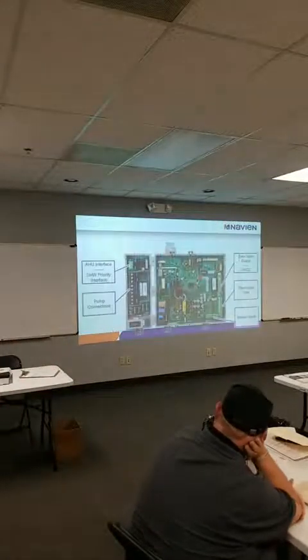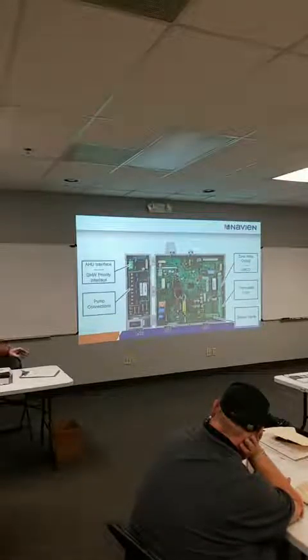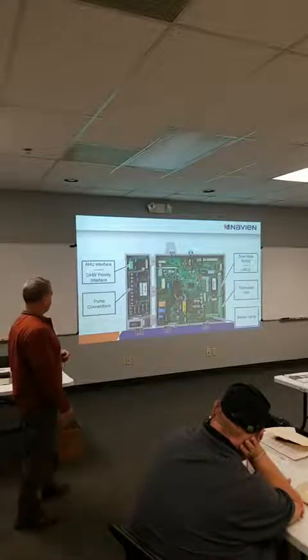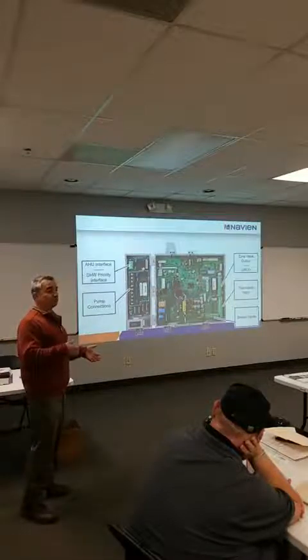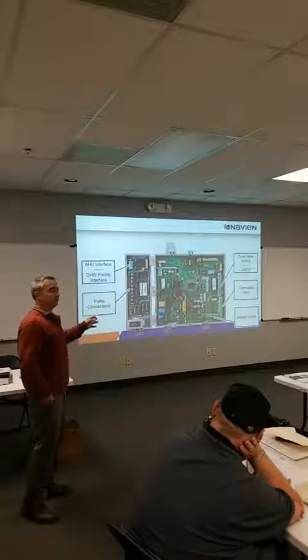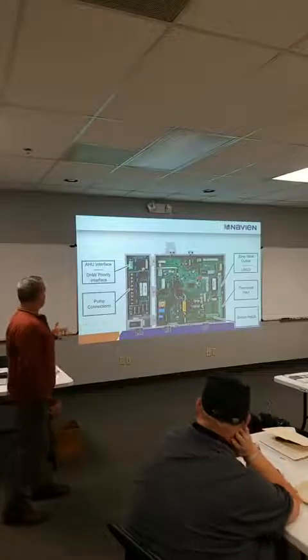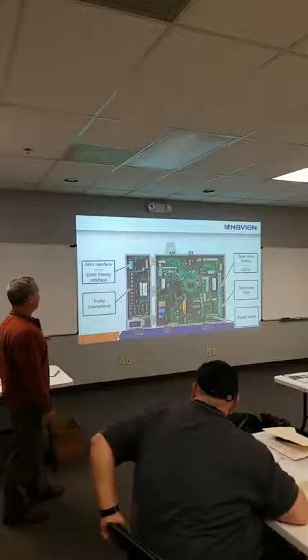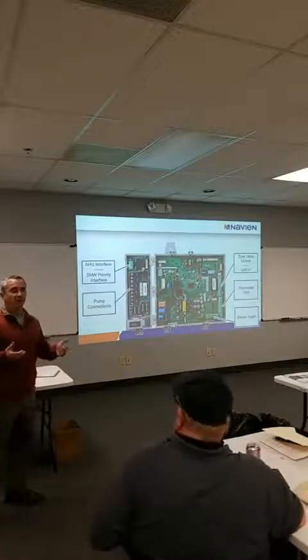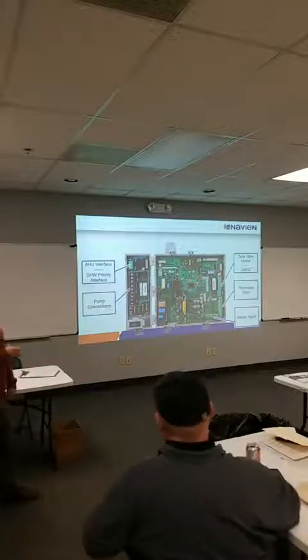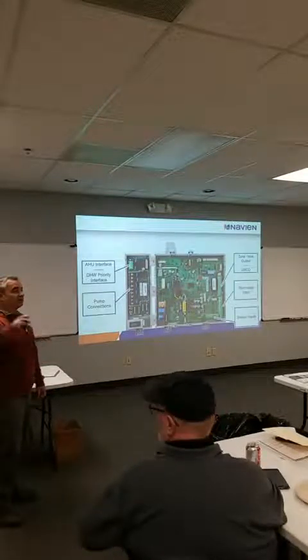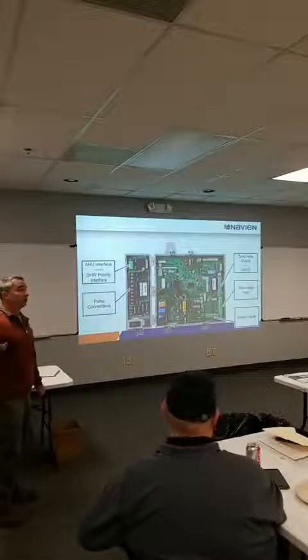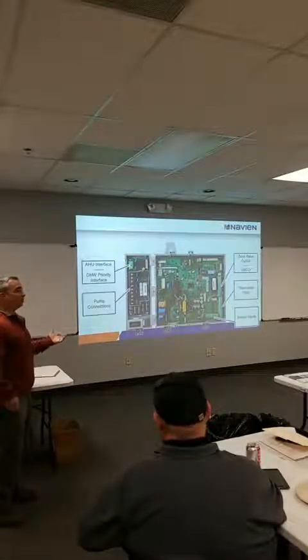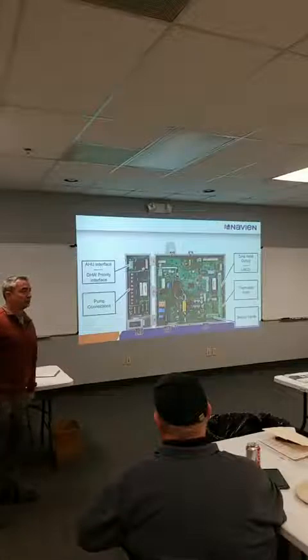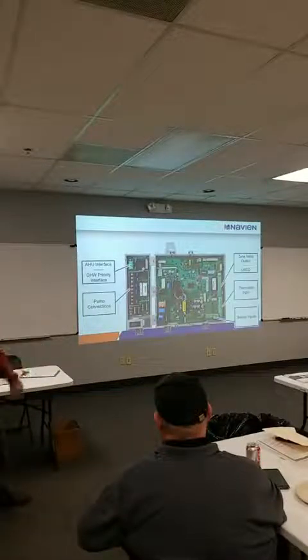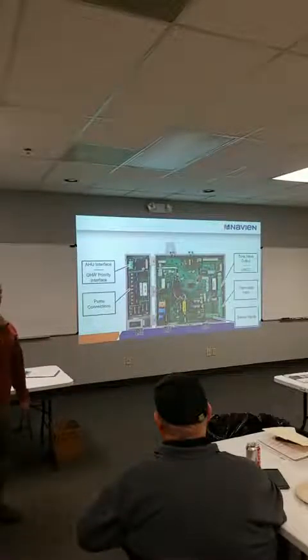So this unit itself will do up to 3 zones outside of your boiler pump. So it'll take care of the boiler pump and then 3 zones of heating, either zone pumps or zone valves. You can do an air handler. You can do domestic hot water again and give it priority temperature, or you can use that domestic hot water port for a second temperature zone if you really want to. So if you have a radiant floor zone and maybe baseboard zone or something, you could do two different temperatures and give one priority over another if you wanted to, if you get a call there.